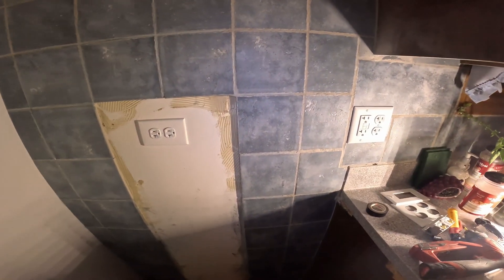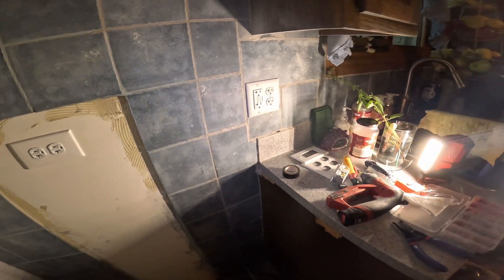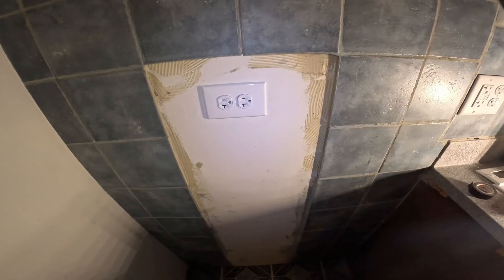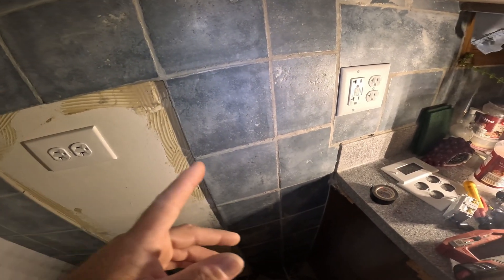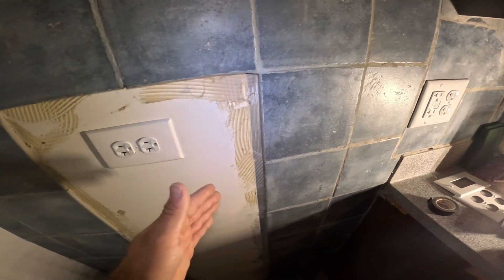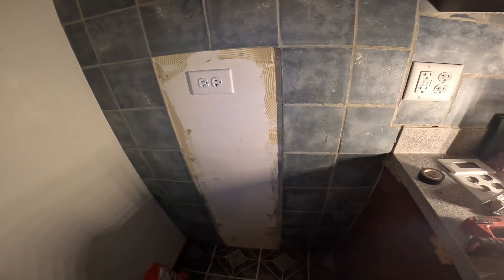I ended up changing it — I don't really like having a GFCI behind the fridge. I automatically thought I needed GFCI because the sink is right here, and within six feet you need a GFCI. But this outlet isn't really accessible, so that should be fine. I mean, really, who wants to pull out a fridge every time? Those GFCIs don't trip all the time anyway.